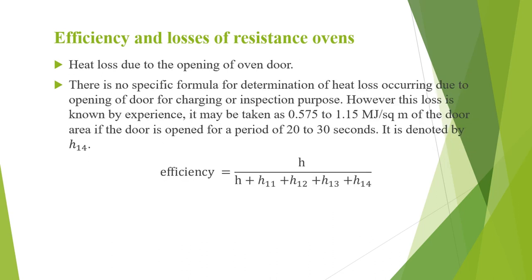Heat loss due to opening of the oven door, denoted H14: there is no specific formula for this loss, but it is known by experience and taken as 0.575 to 1.15 MJ per square meter of door area if the door is open for 20 to 30 seconds. Therefore, the efficiency is given by H / (H + H11 + H12 + H13 + H14).